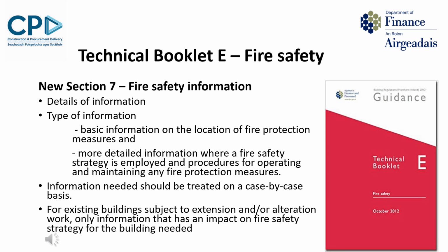The new Section 7, entitled Fire Safety Information in TBE, is guidance to the new Regulation 37A, Fire Safety Information in Part E of the Building Regulations. An extensive list of details of information is given in the section. For most buildings, basic information on the type and location of fire protection measures in a building should be sufficient. A more detailed record should be provided for buildings where a fire safety strategy is employed, along with the procedures for operating and maintaining any fire protection measures.